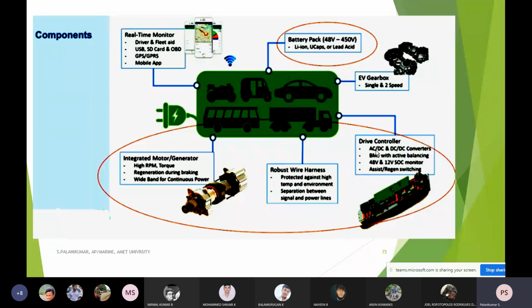Whenever temperature goes above 45 or below 15 degrees, we automatically need a battery management system, meaning external cooling or heating arrangement, so that I can get assured performance. Otherwise, the energy density in the battery will drastically come down.